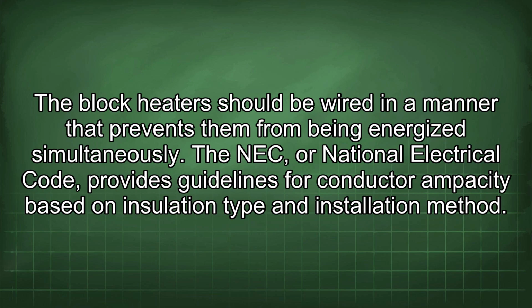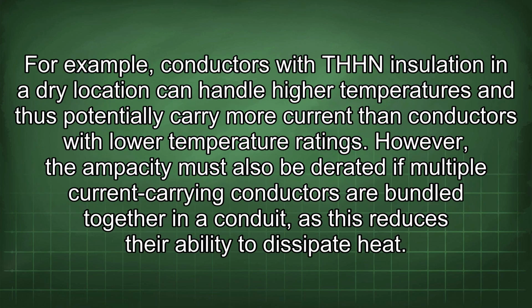The block heaters should be wired in a manner that prevents them from being energized simultaneously. The NEC, or National Electrical Code, provides guidelines for conductor ampacity based on insulation type and installation method. For example, conductors with THHN insulation in a dry location can handle higher temperatures and thus potentially carry more current than conductors with lower temperature ratings.